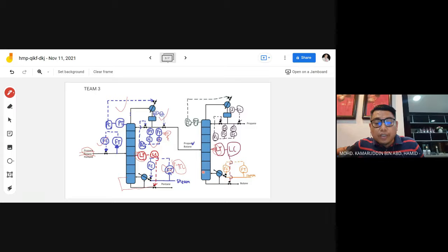You're not measuring at the top here, you're measuring down here. Okay, don't flow control the steam flow rate. You need to control directly the temperature at the bottom of your distillation column. This is okay, this is right, and again, usually we use the ratio, if there is a requirement for you to measure the distillate here.